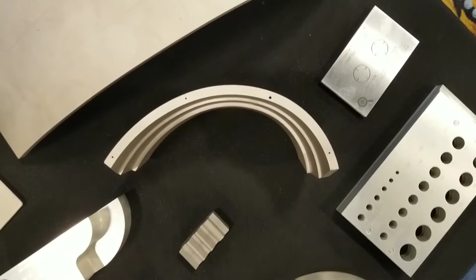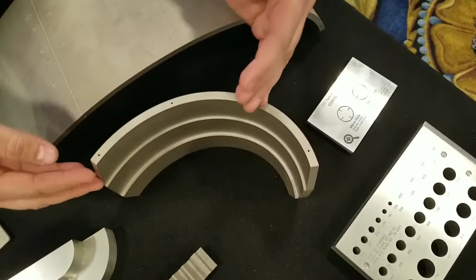But anyway, this is a bunch of ASME Section 5 calibration blocks for pipe put into one. What it does is allow you to calibrate for scanning of long seams. If you have a mind for how things are machined, you might think they put this on a lathe and turned and bored the ID to get these steps in here. But it's not, because if you look at it closely, it's actually 3 different radii stitched together at these points. So you have a smaller radius here, and you get a larger radius out here as it goes back.